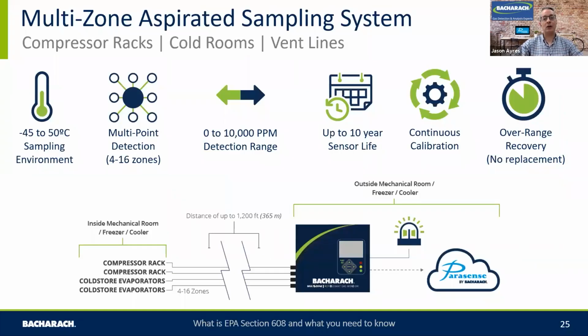And in terms of the technologies that are available, the Bacharach multi-zone gas detector is probably the best in class system out there for low-level leak detection. It has some key benefits for you as an organization for detecting refrigerant. It can be used in any environment, so it doesn't matter if it's cold or hot. The sample location of the detection of that leak, it can work in all those areas. We talked about detection points earlier. The more detection points we have, the closer to the leaks, the better and quicker that we can respond to alarm. The aspirated multi-zone system allows you to deploy more points of detection much more cost effectively and much cheaper.